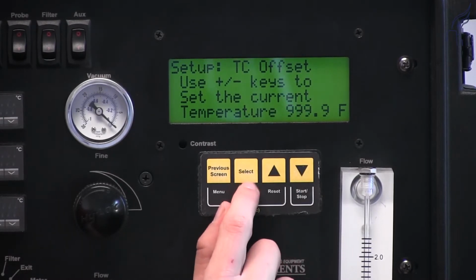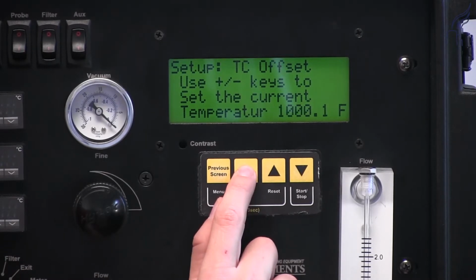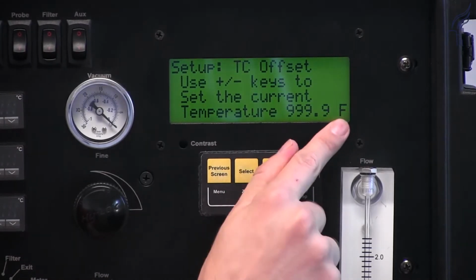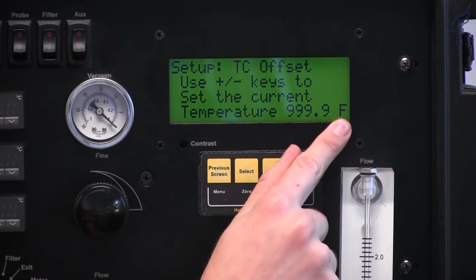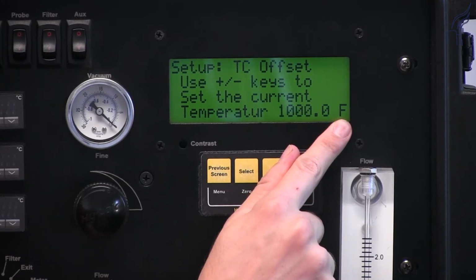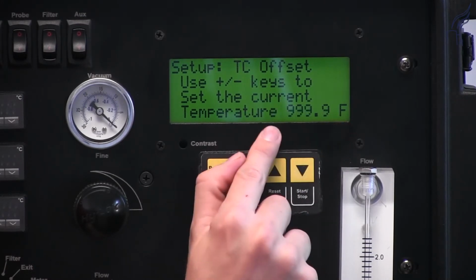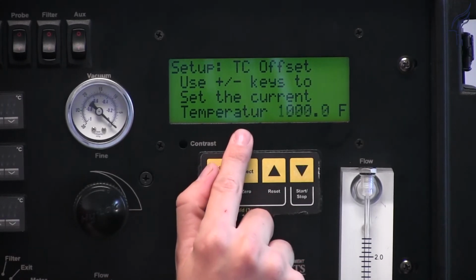Once I'm around 1000 degrees, I can press select to capture and save the value, and an asterisk will appear here that signifies this. These calibrations transition to every channel of the thermocouple switch, so you won't need to do this on each channel. You can pick any channel that you choose.